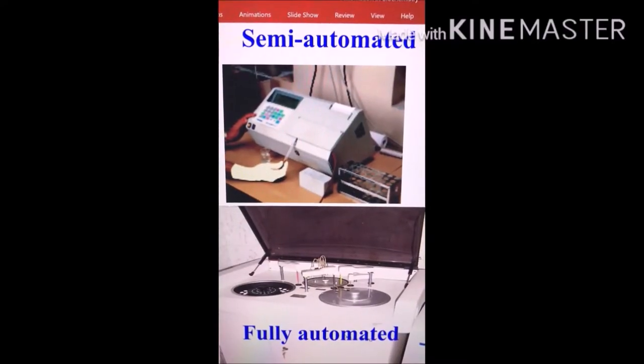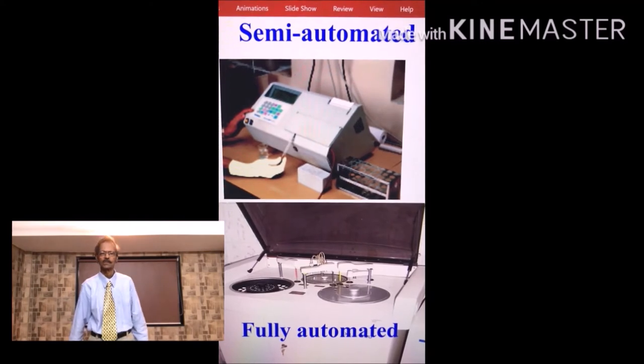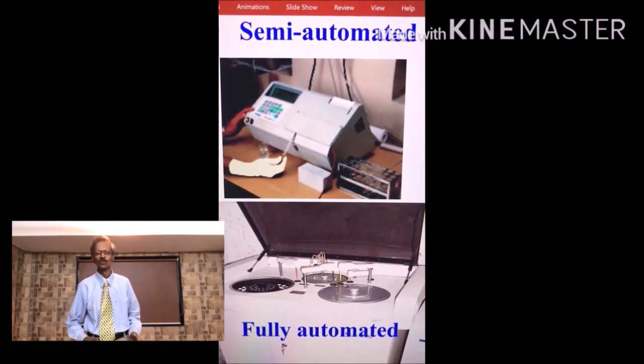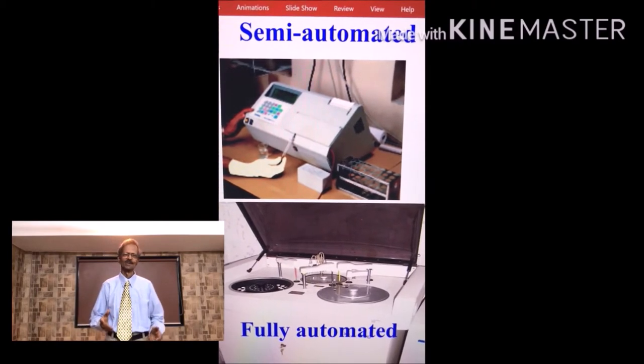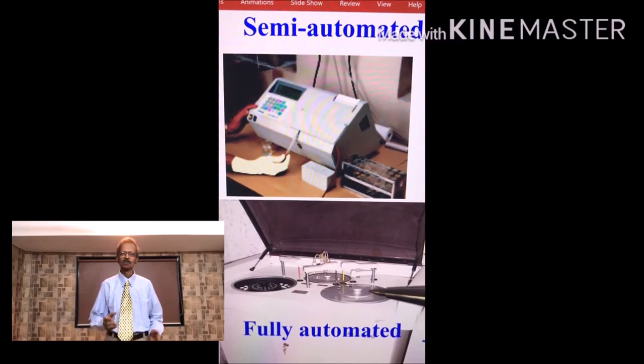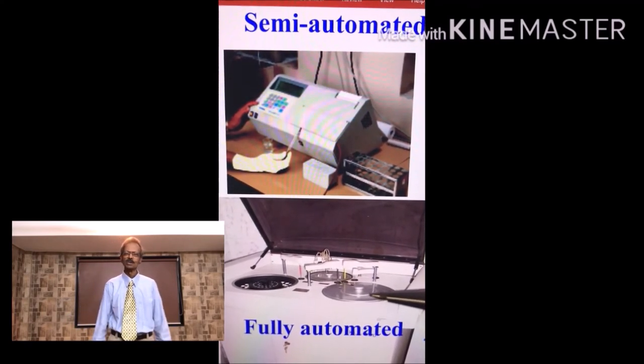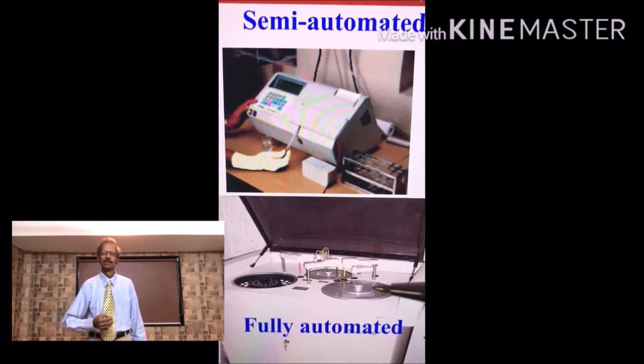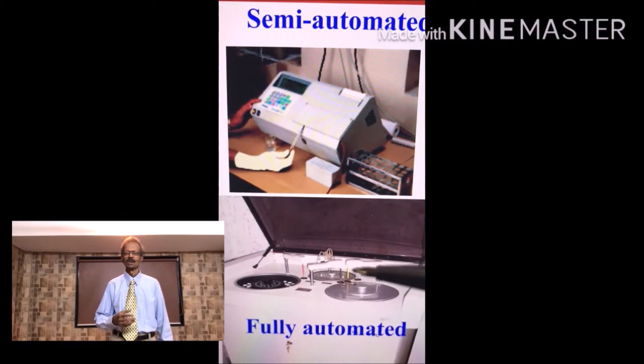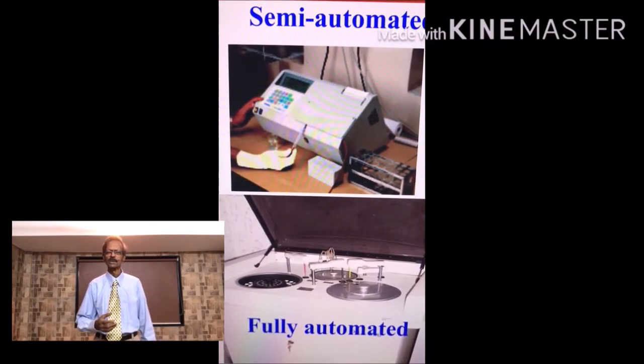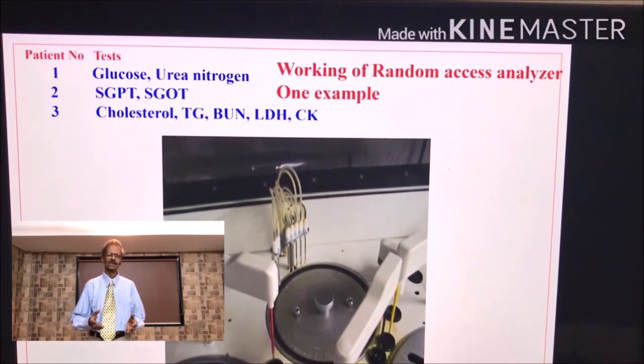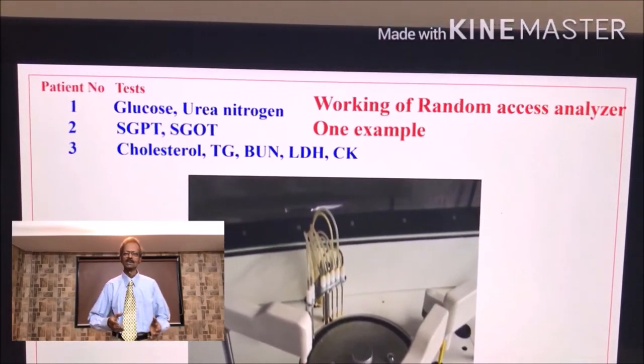Well, first you try to understand the difference between semi automated instrument and fully automated instrument. See this sampler where samples are placed, reagent carousel where the reagents are stored, and reaction carousel. These three things are not present in semi-automated analyzers.